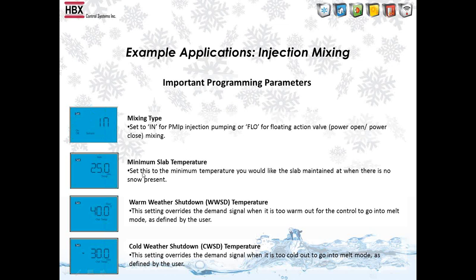Minimum slab temperature. So this is the idle temperature. So minimum slab temperature is your idle temperature that you would set. So like I said, you can set it around 25 to 28 if you want it to be quick reacting when it does see snow, or if somebody doesn't want to pay for idling the slab for 90% of the winter, then you would set this really low. So let's say -20. So warm weather shutdown, most people set it to around 36, 38. Cold weather shutdown depends again on how you design the system.